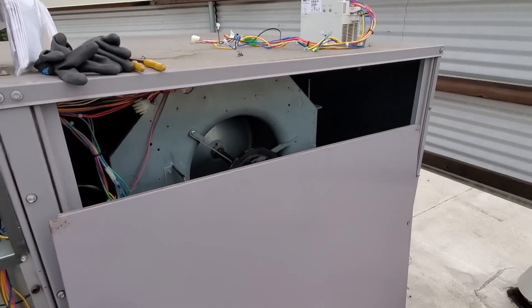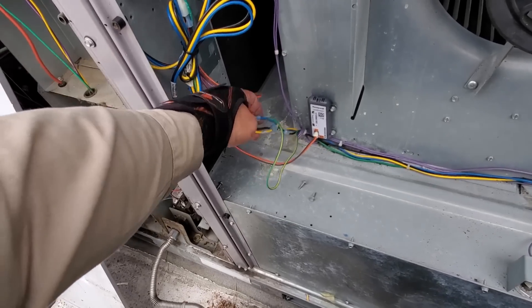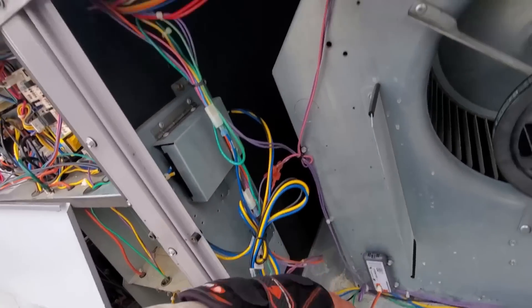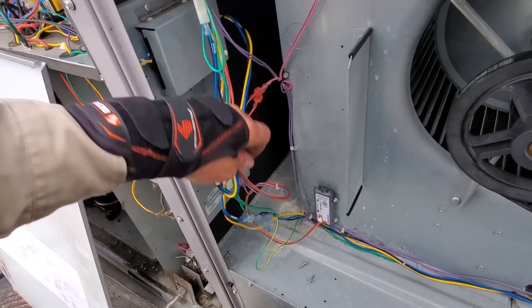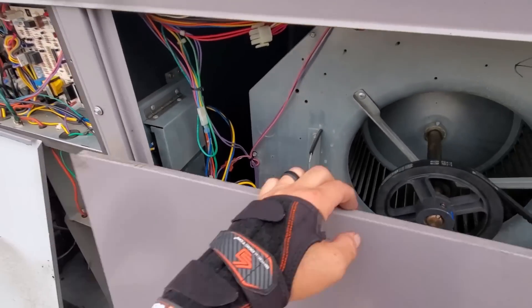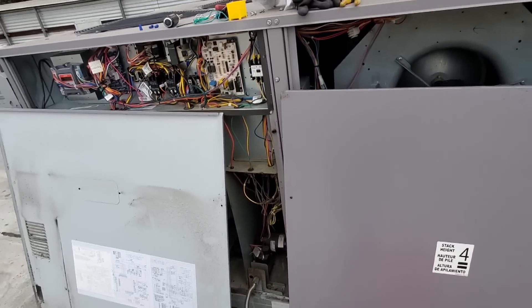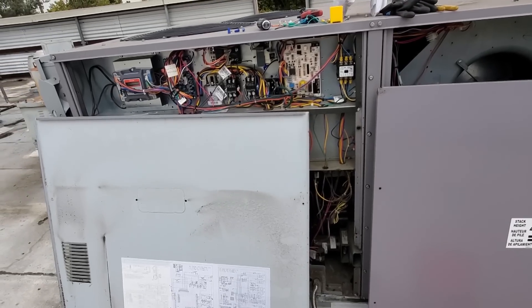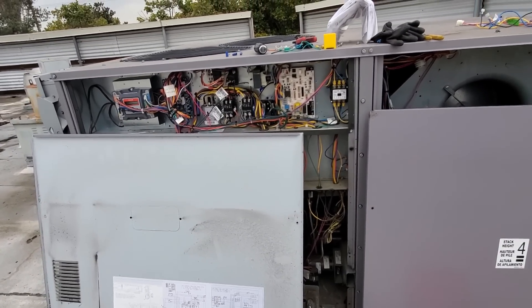Carrier is pretty smart — they were nice enough to put male-female connectors so with this drive you could literally just bypass it by unplugging these and plugging into the incoming side. So they do realize that there's going to be drive failures. Other manufacturers will do that too. Lennox does that. Some of the Lennox L-series or Energence units actually have an auto-bypass on their drive, so if it senses that the drive's failed it'll bypass the drive internally through a relay.